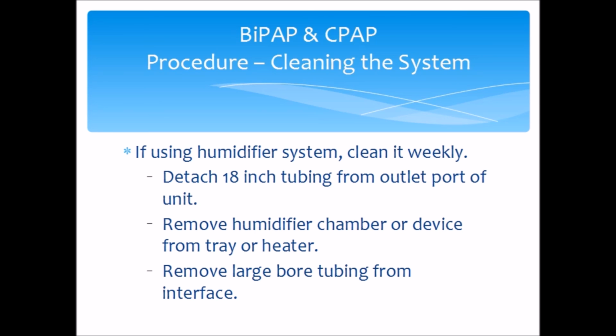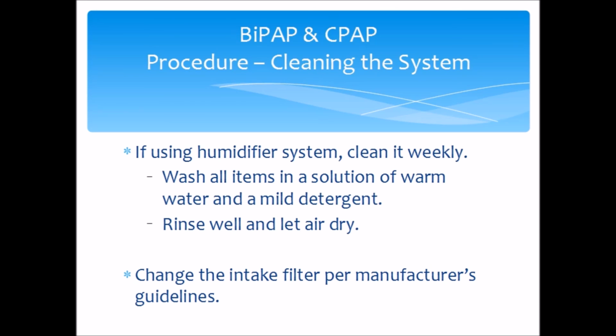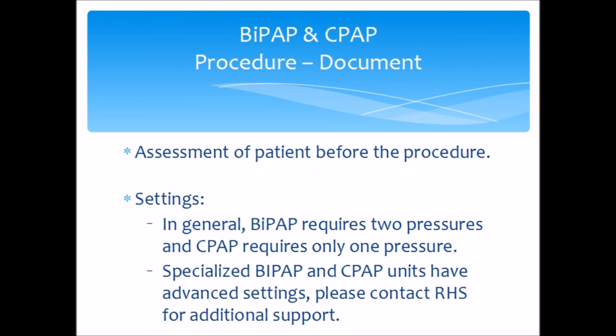Detach the 18-inch tubing from the outlet port of the unit. Remove the humidifier, chamber, or device from tray or heater. Remove the large bore tubing from the interface. Wash all items in a solution of warm water and mild detergent. Rinse well and let air dry. Change the intake filter per the manufacturer's guidelines.